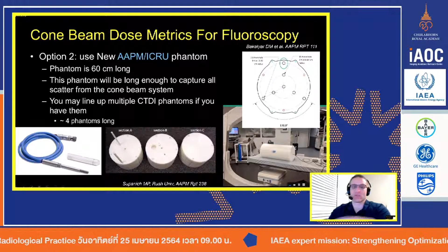But you've got to understand it's going to take about 4 CTDI phantoms taped together to get the same equivalent length. Small difference is this is actually made out of polyethylene, not acrylic. So this material is tissue equivalent. It's actually soft tissue equivalent. So it will create scatter more similar to our abdomen than the CTDI phantoms. All right, so all of that aside, how would we use this phantom if you were so adventurous?